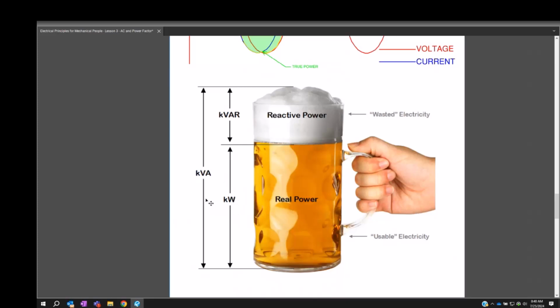So if I have a generator pushing nothing but heating up a bunch of things, it's nothing but kilowatts—I just got to make sure of that. But if I've got a ridiculous amount of motors on that generator, I need to understand how much kVAR I need in order to operate those motors.